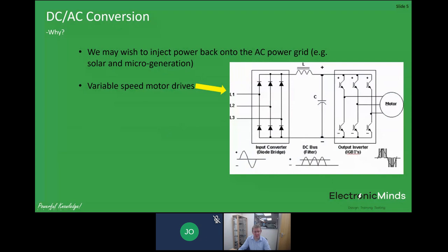Another very common application is variable speed motor drives. Most high power motors operate on three-phase AC, and traditionally you would just run them from 50 Hz mains — but that's a very inefficient way to operate for variable speed. In a variable speed drive, you have an input AC to DC stage where the three-phase mains input is converted to a high voltage DC link, and then a three-phase inverter on the output creates a variable frequency AC supply to the motor, allowing a much more controllable and efficient system.